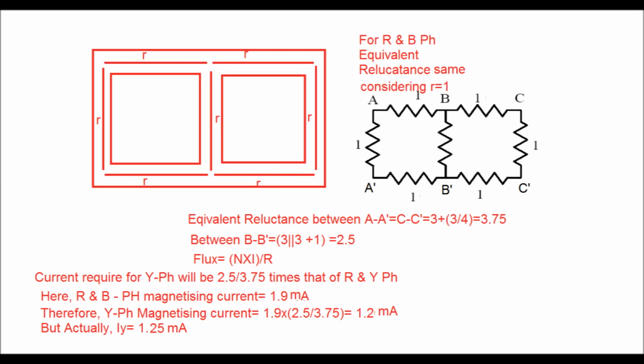Now flux is equal to Ni by R, where R is the reluctance of the core. If R varies, the flux will vary. Therefore, to maintain a steady flux in the core, the current varies for red, yellow and blue phase. For red and blue phase, since the reluctance is the same, the current is almost the same. But in case of yellow phase, since the reluctance is different, the flux varies. To maintain a steady flux, the yellow phase will draw a different current from the supply.